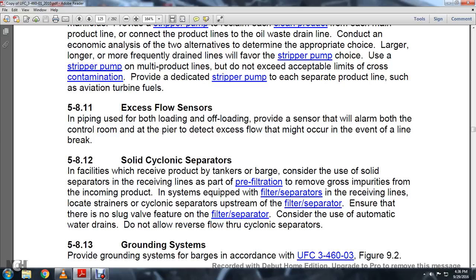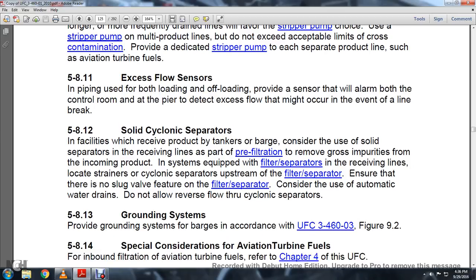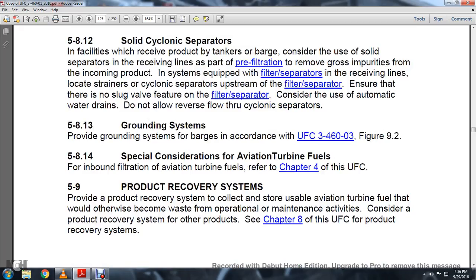The system is equipped with a filter separator for the receiving lines. Locate strainer cyclonic separators upstream of the filter separator. Ensure that there are no slug valve on the filter separator. Consider the use of automatic water drains, which does not always apply to the cyclonic separators.